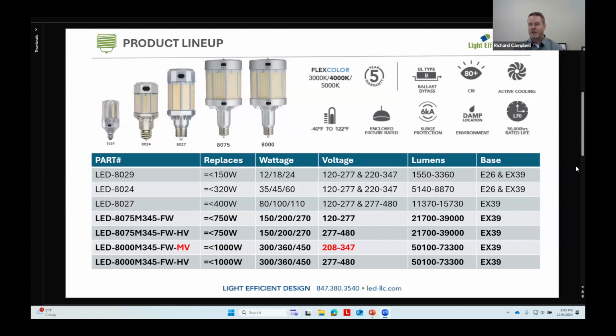So our low voltage options are 120 to 277. Our new medium voltage, which is only available on this lamp right now, is 208 to 347. And our high voltage option is 277 to 480. We have to do this on this lamp because with the 1000 watt replacement and 450 watts, we cannot go down to 120 because the amp draw gets too high.